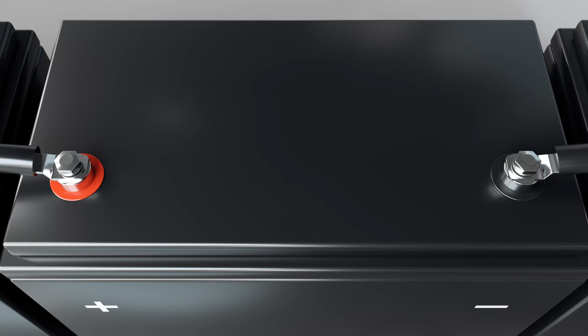Then connect the battery connecting cable to the battery of a string. Remove the pole screws and washers from the battery and insert the ring washers onto the corresponding poles on top of the battery connectors. Then reinstall the washers and pole screws.